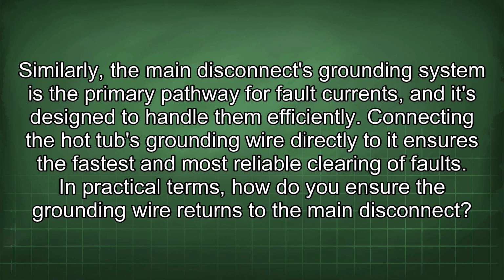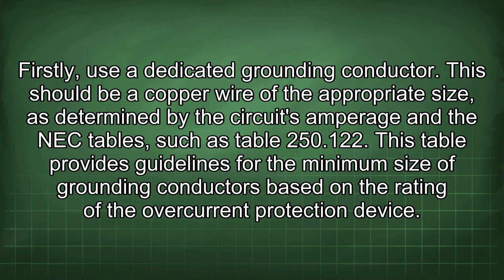In practical terms, how do you ensure the grounding wire returns to the main disconnect? Firstly, use a dedicated grounding conductor. This should be a copper wire of the appropriate size, as determined by the circuit's amperage and the NEC tables, such as Table 250.122. This table provides guidelines for the minimum size of grounding conductors based on the rating of the overcurrent protection device.